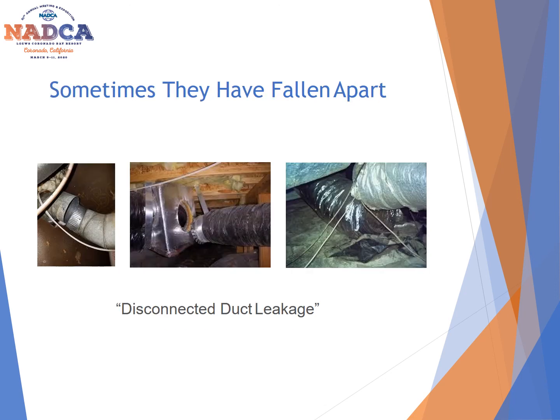Now, the other reason why doing inspections is extremely important when you're dealing with HVAC systems and you're trying to determine why things may not be working properly is you have to look to make sure the system is put together properly. These are perfect pictures of situations where duct has been knocked loose for one reason or the other, and it is just completely disconnected. And that could be a big reason why you have your leakage, obviously, and also why specific areas are not cooling. So you need to keep an eye out when you are working in residential properties or even on commercial properties for these exact situations so that they can be addressed.